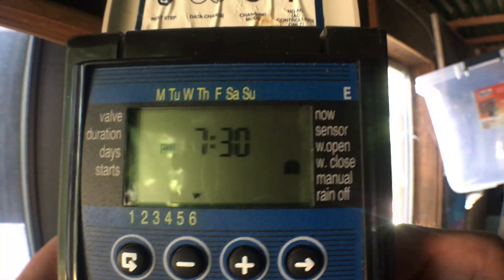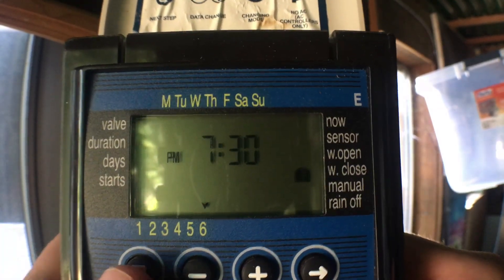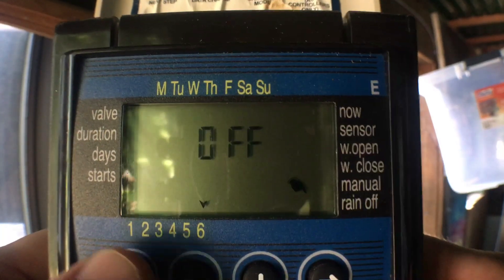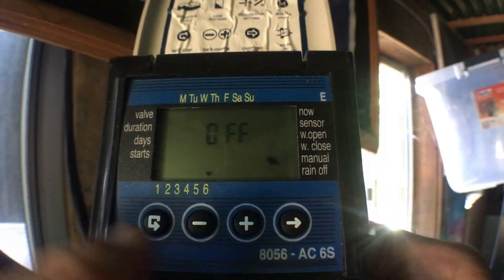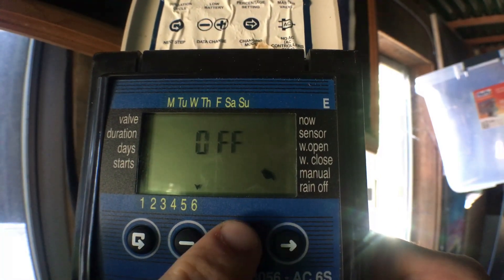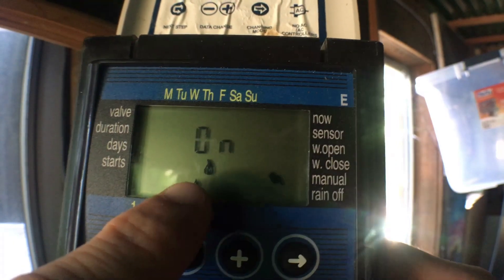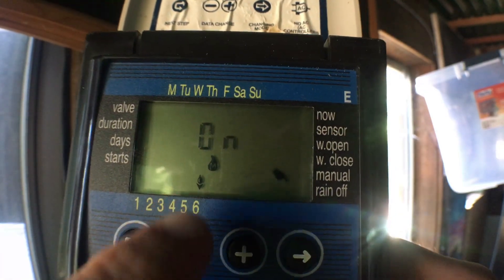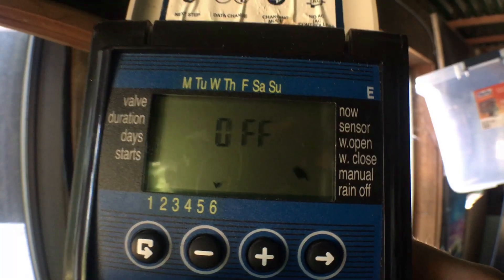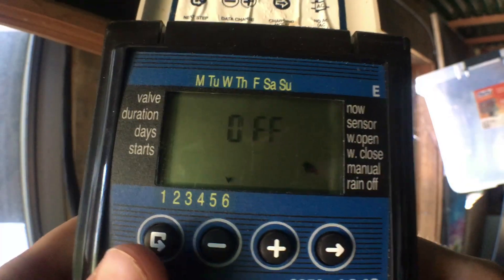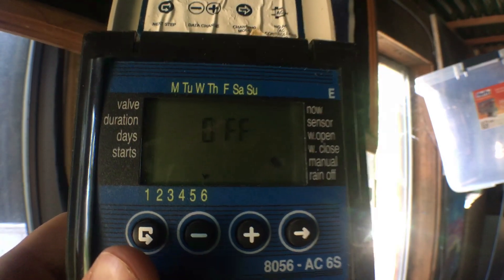I can change either of these values by hitting the arrow and adjusting the time, but I'm good with that. Then there's manual — if I wanted to just punch it and make it work right away. Right now it's set to off, but all I have to do is hit plus, then plus again, and it goes to on. We get the little water droplet over valve six showing it's working. I can switch it back to off by pressing minus. It'll only run for as long as the current program is scheduled.